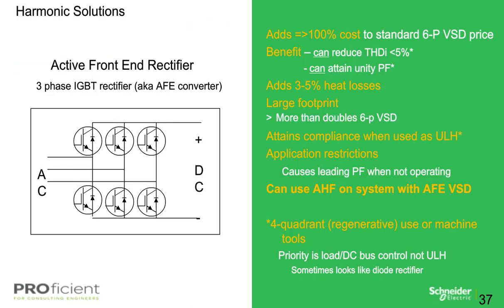Okay, so moving on to some of the details of the active front-end rectifier, which are typically used in VFD and UPS applications. These could add a substantial footprint to your equipment as well as substantial cost to your overall system. And they essentially double the size of your current 6-pulse due to the incoming passive filters required to suppress the percent THDV and the high frequency switching noise caused by the IGBT.